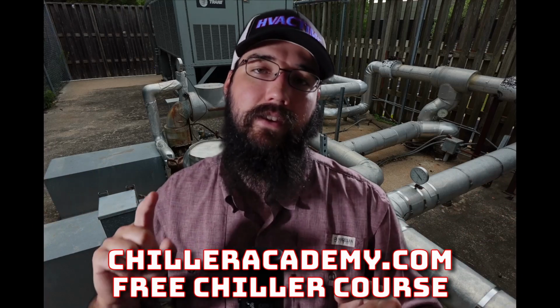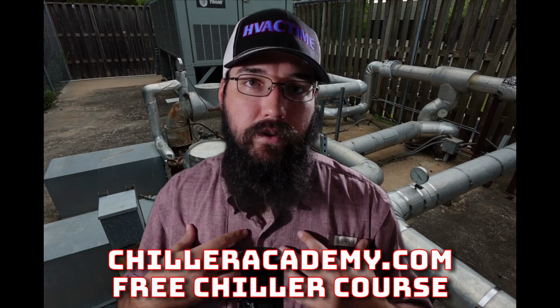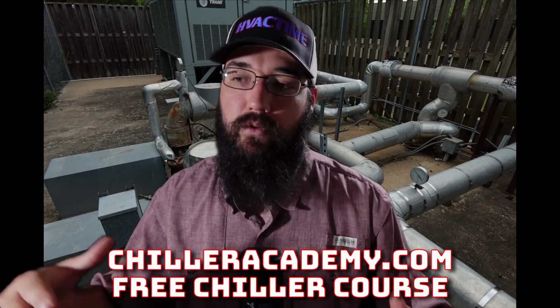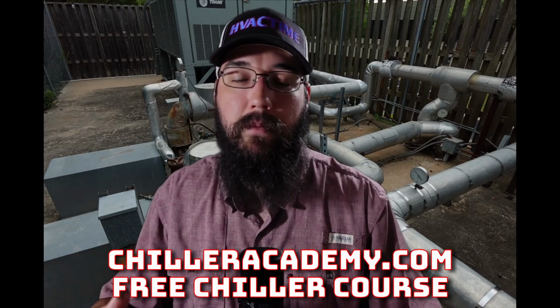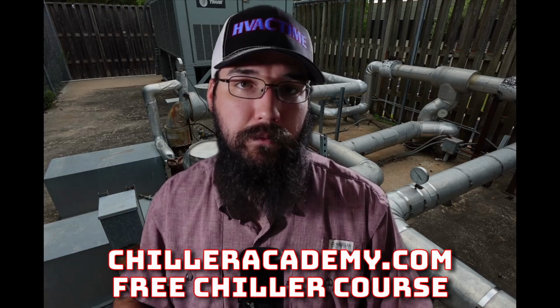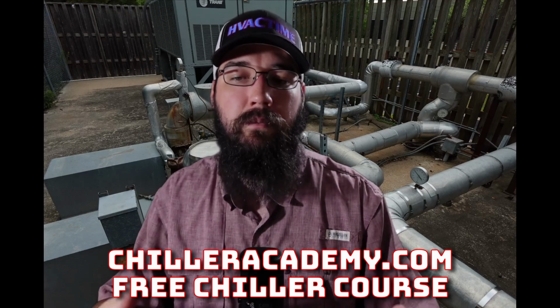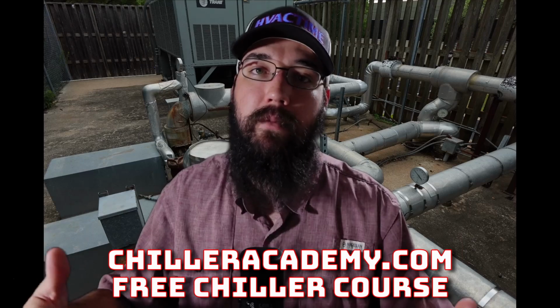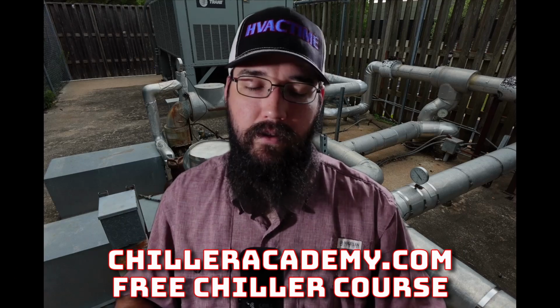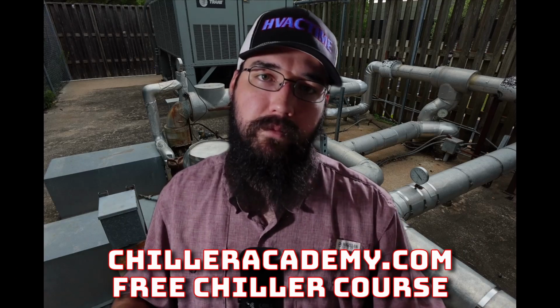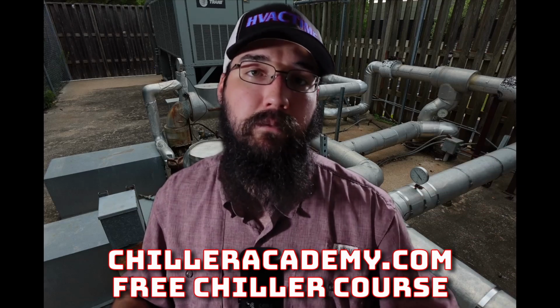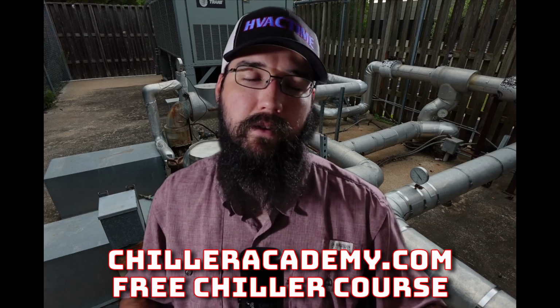Whereas for my grease gun, a lot of smaller motors, we're talking less than 20 horse, it may only need 2 pumps every quarter. And it's something that small. It doesn't take a tremendous amount typically. But if you were to do a purge method, you may put 5-10 pumps. Well, maybe 10 may be a bit excessive.